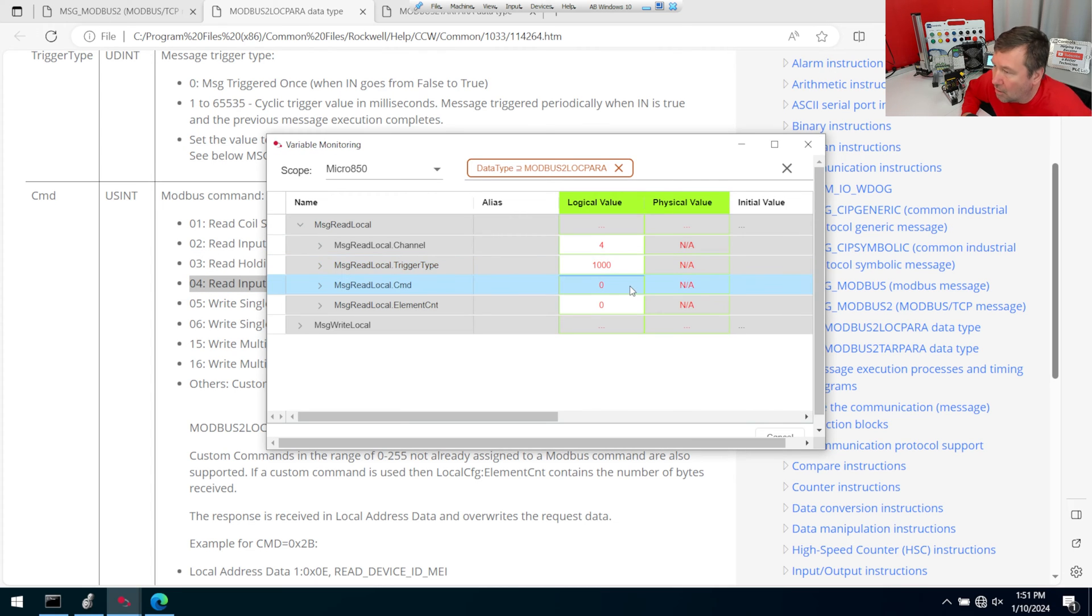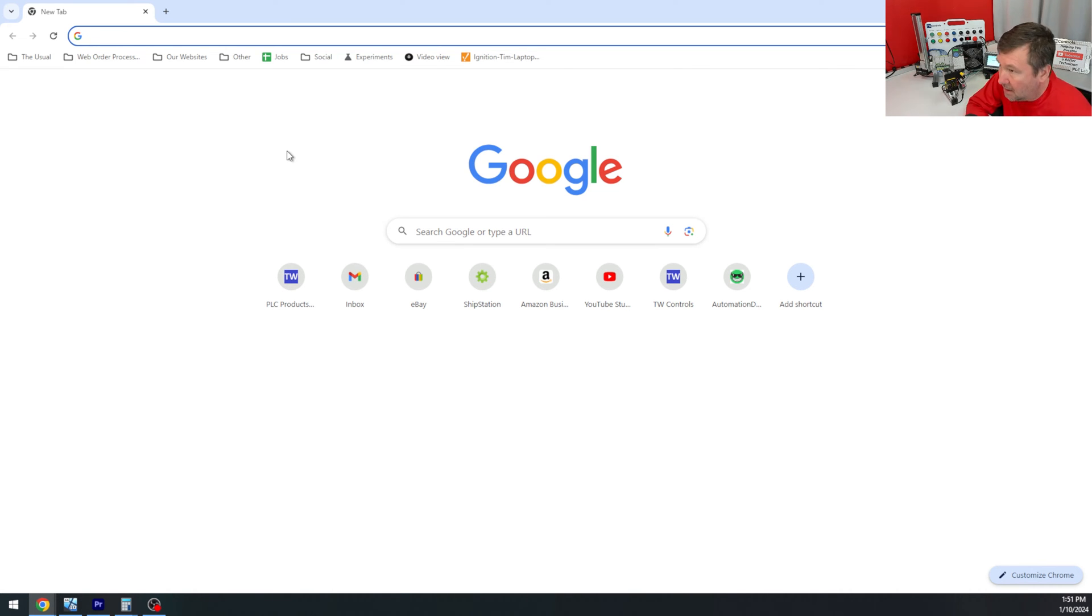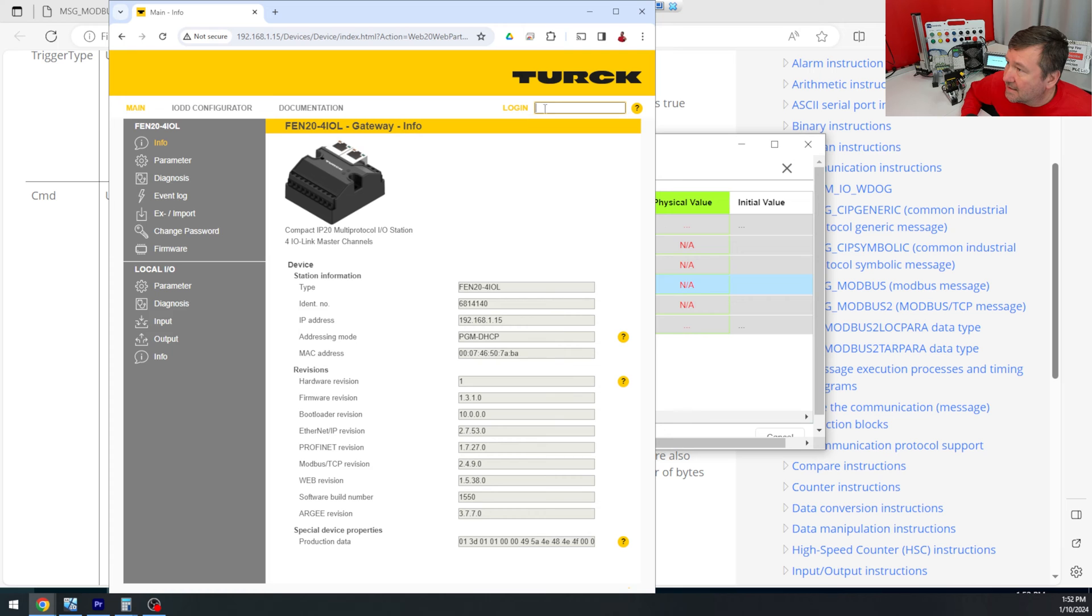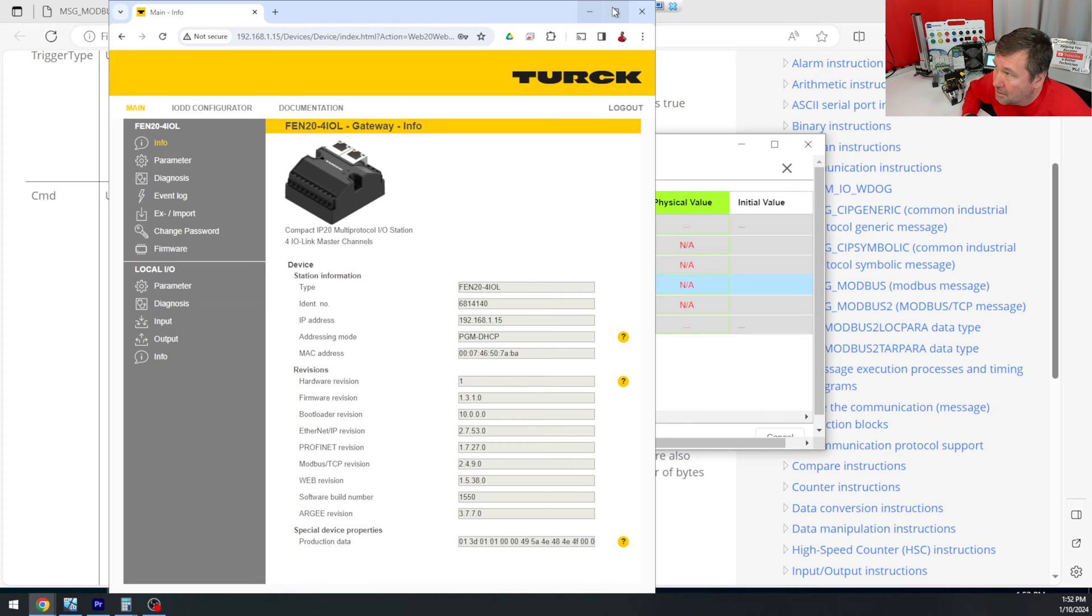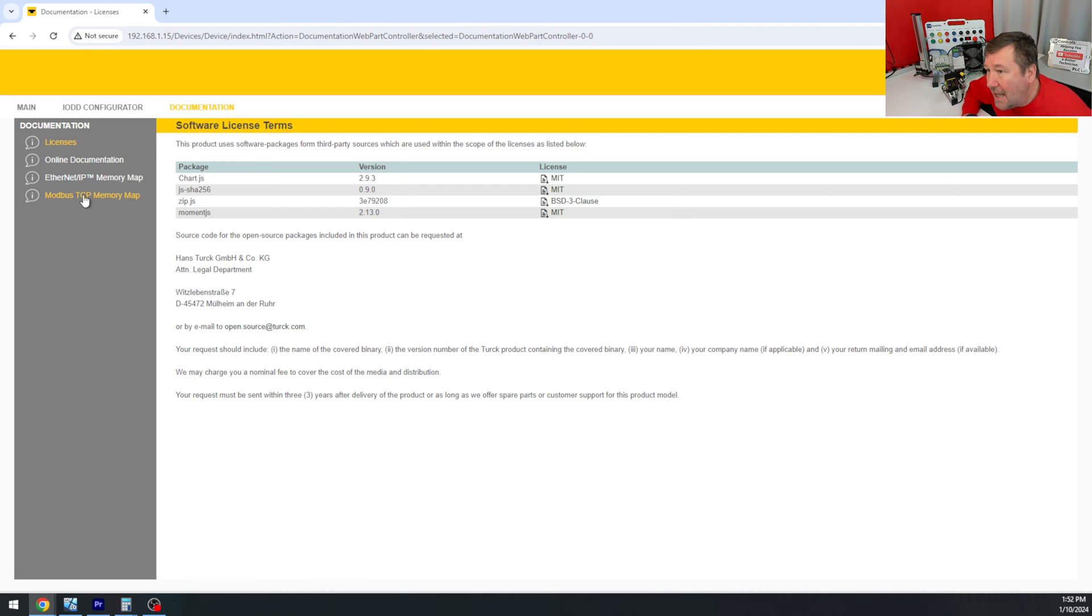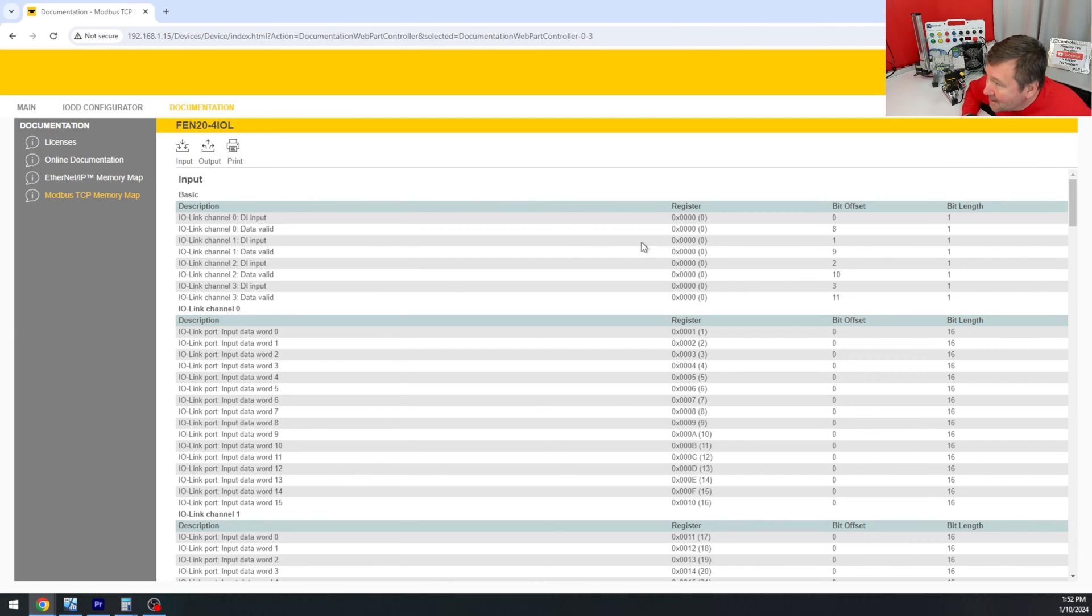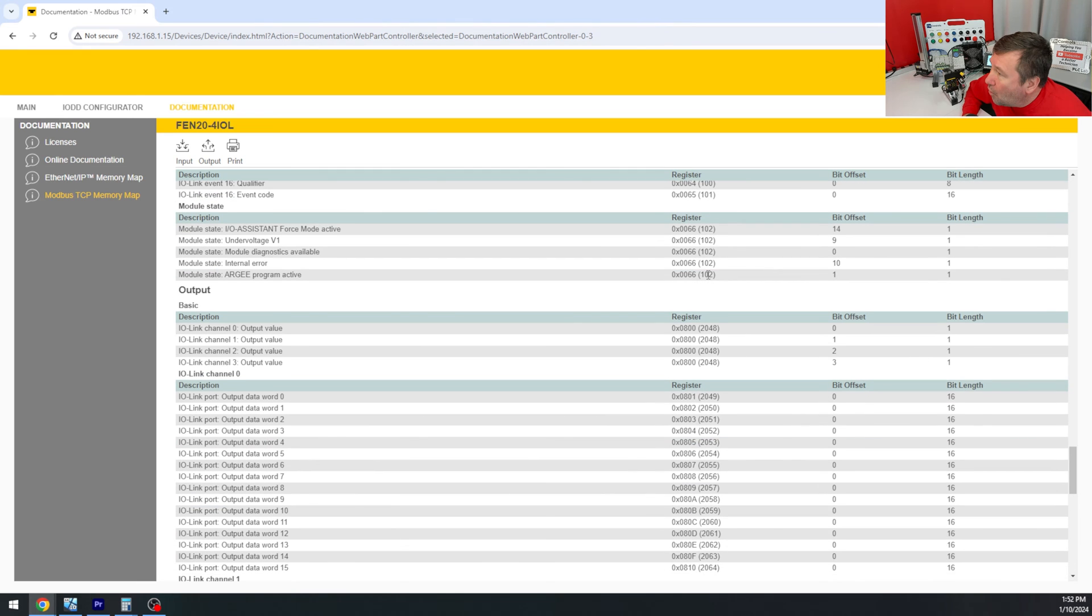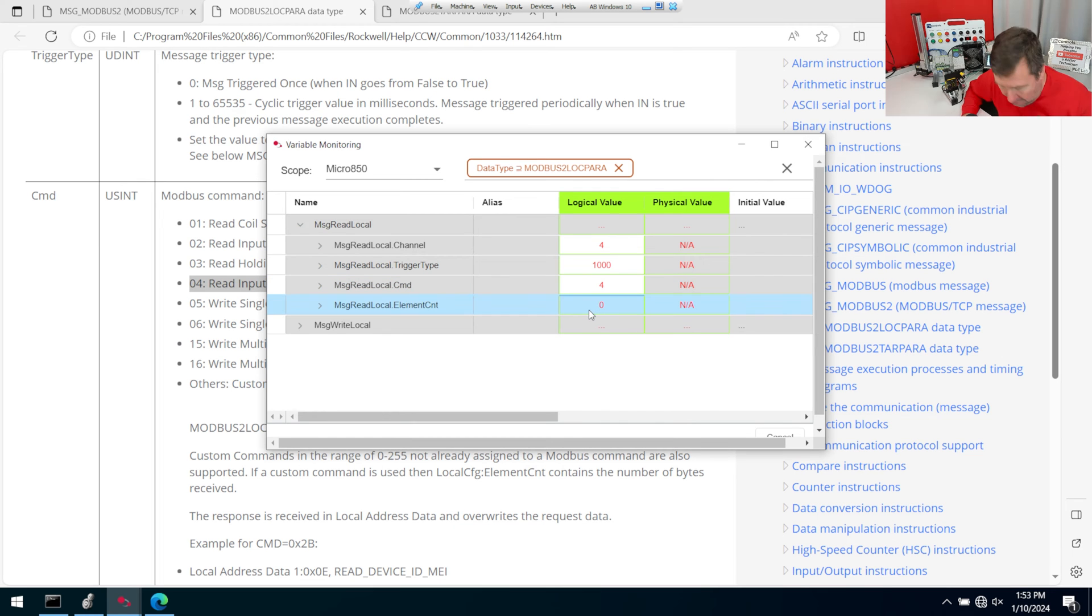And then we have the Modbus command. And this is one of the more difficult ones if you're not familiar with typical Modbus. But we want to set our command for reading these inputs to 4. So we're going to set our read local command to 4. And we have an element count. Now, to figure out our element count, we're going to go to the web browser and look at the IP address of our IO link module. And if you're using our trainer, its default IP is 192.168.1.15. And then let's go ahead and log in. That's in the top right here. The default password is all lowercase password. And it does recommend you change it. And I would recommend you change it. But I'm going to leave it at its default. That way it arrives to you with that password in it. And then go to the documentation up here. And we want the Modbus TCP memory map. And here is the whole layout of our Modbus data that we're going to be reading. So it does start at 0. And it's going to go to 102. So 0 to 102 is going to be a length of 103.